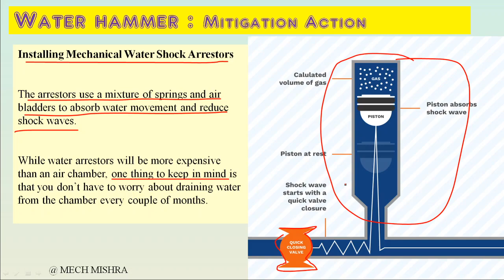The arrestor uses a mixture of spring and air bladders to absorb the water movement and reduce the shock wave. While a water arrestor will be more expensive than the air chamber, one little thing to keep in mind is you don't have to worry about draining water from the chamber every couple of months. So this chamber, or sometimes we call it a surge tank, should be provided near the quick closing valves, and that will absorb the shock, and that's the way you can mitigate water hammer in a better way.